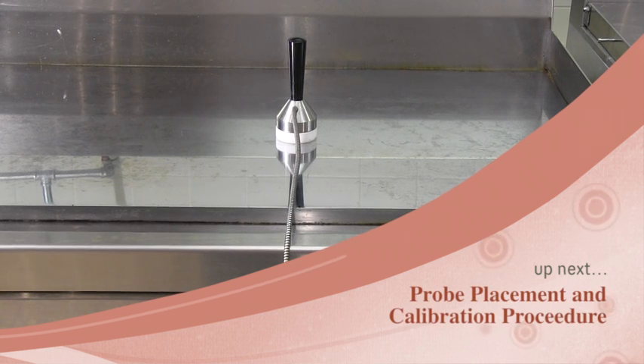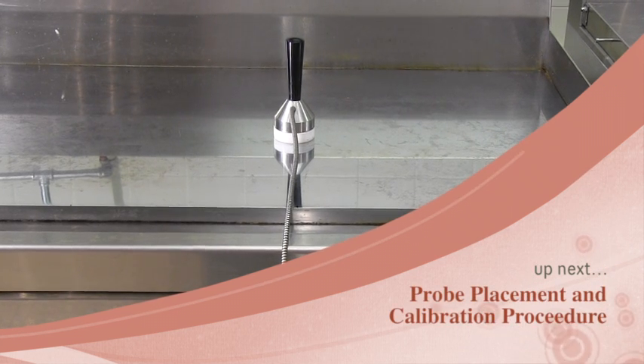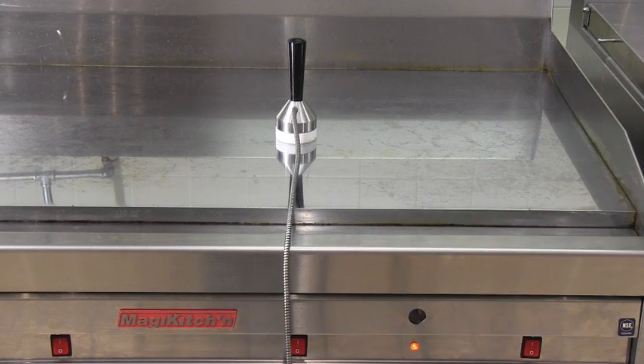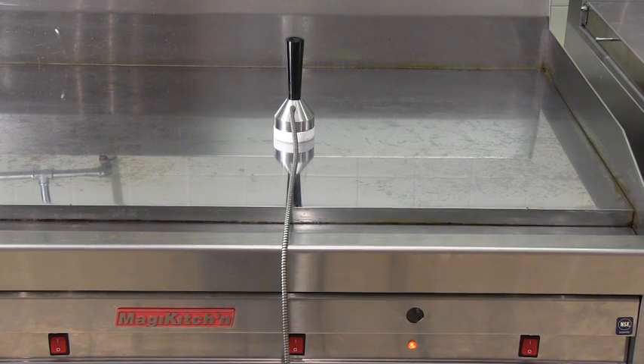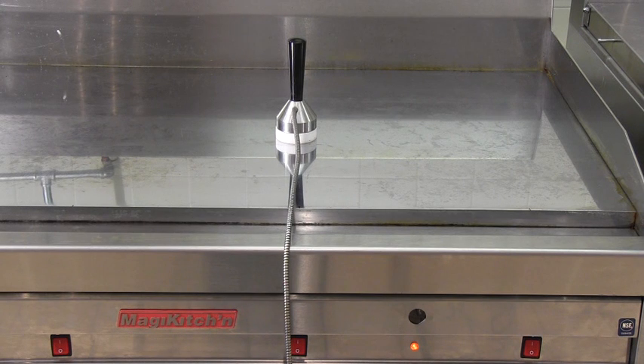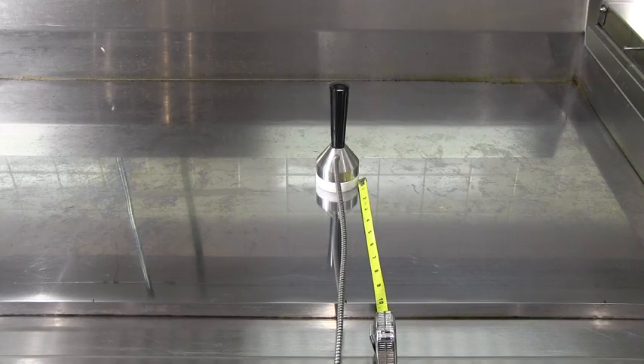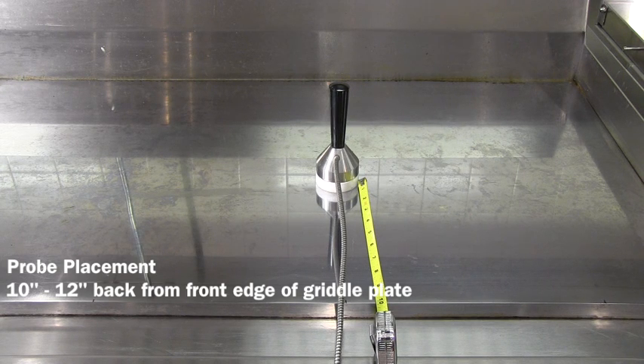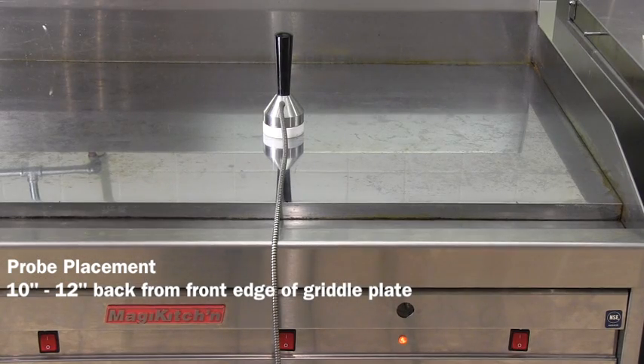We will now review proper temperature probe placement and calibration procedures. It is very important to place the surface temperature probe in the correct positions on the griddle surface so that you can get the proper temperature readings. The surface temperature probe you are using should be placed approximately 10 to 12 inches back from the front lip of the griddle plate, in line with the red on-off switch for the heat zone you are wishing to calibrate.